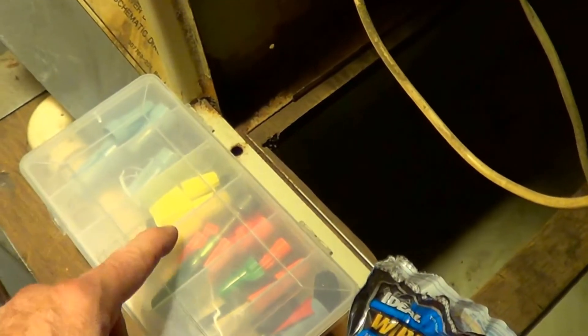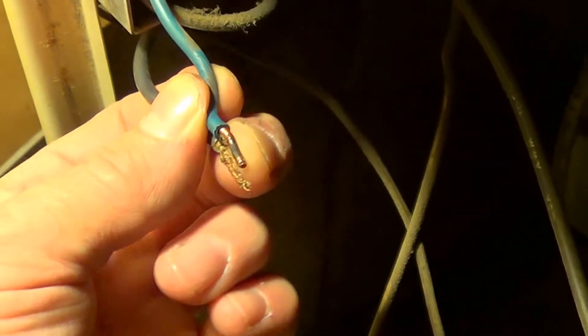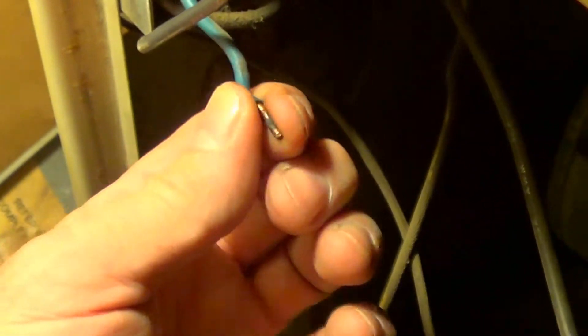That probably didn't even really go in very well. I'm going to use a proper wire nut, use a yellow one, and get all this cleaned up and put a bigger wire nut on there so it's actually engaged. You can see the arcing on here and it's all black. It was in a metal box here so it wouldn't really catch anything on fire. It's just kind of a jackass situation. I'm going to clean all that up and put the proper wire nut on there. This blue wire goes all the way back to the 220.